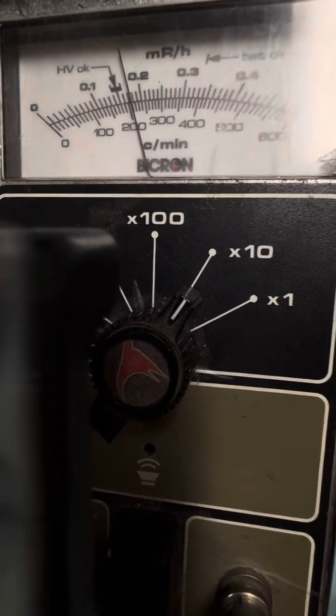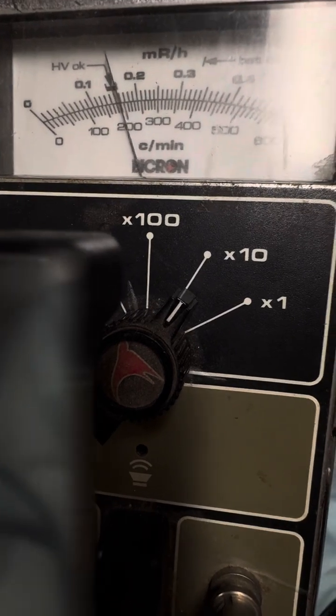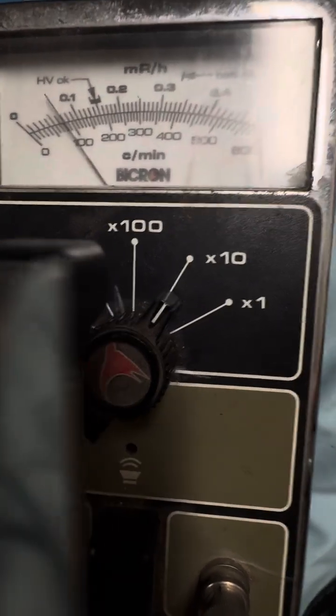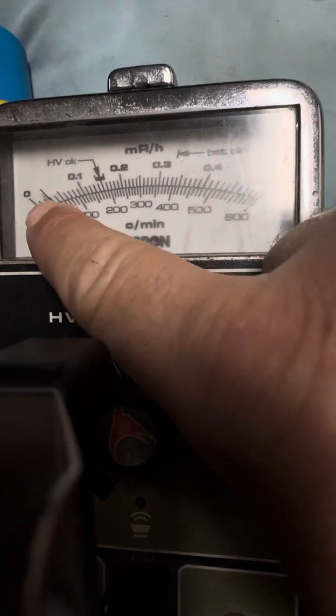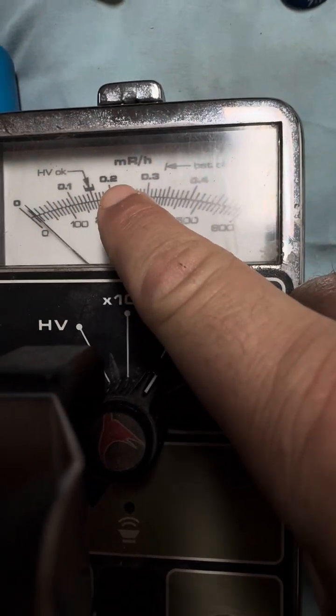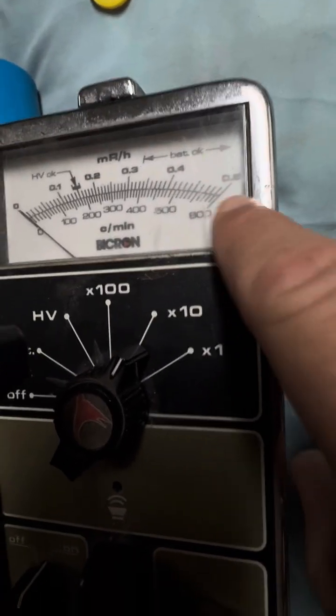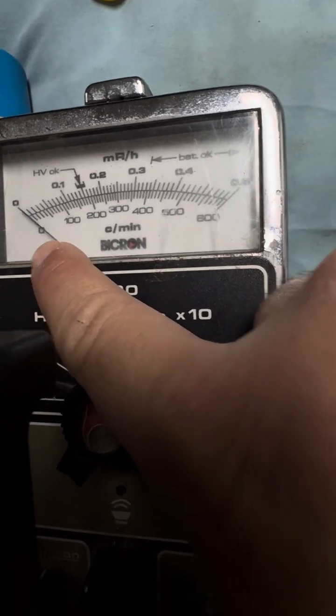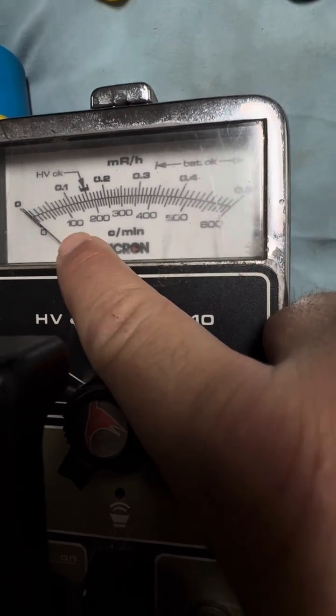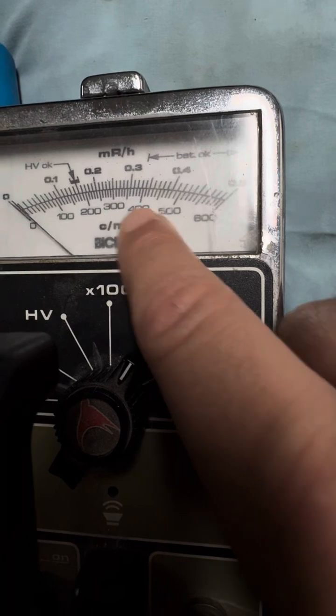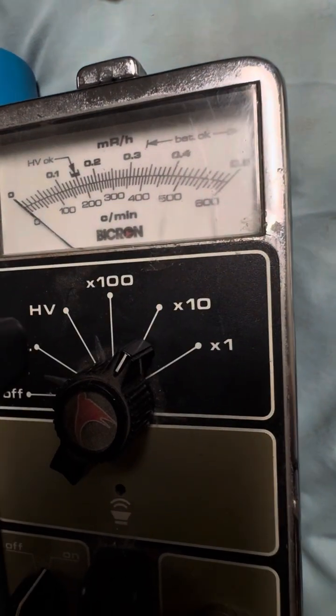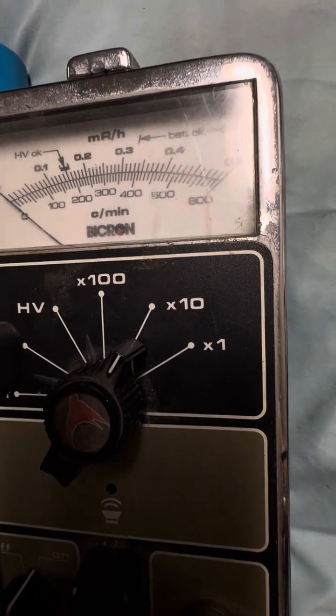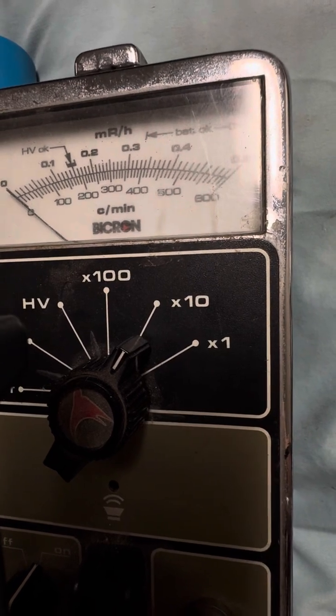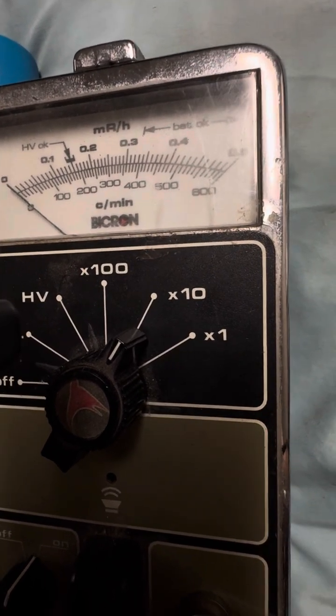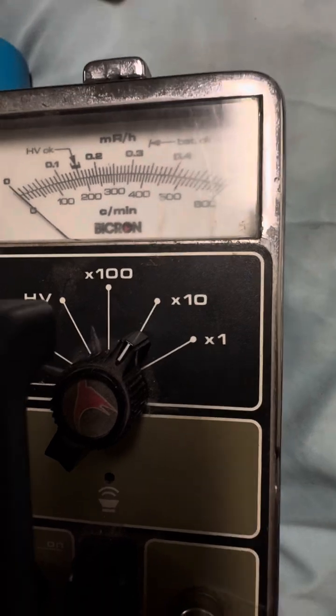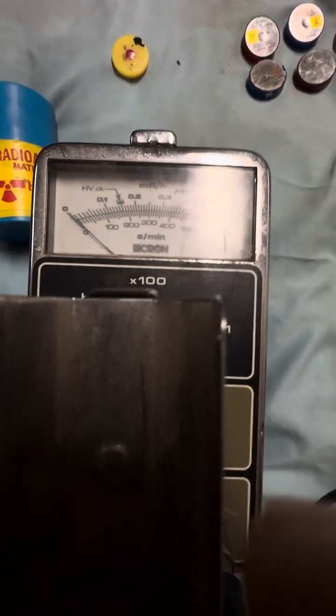But once again, if you do want that HP-270 probe that represents milliroentgens per hour dose, which is the scale you see here, the 0.1, 0.2, etc. This probe is to be used with the counts per minute scale, so 0, 100, 200, 300, etc. It goes up to 600 counts per minute on the X1 scale, 6,000 on the X10, and 60,000 counts per minute on the X100 scale.